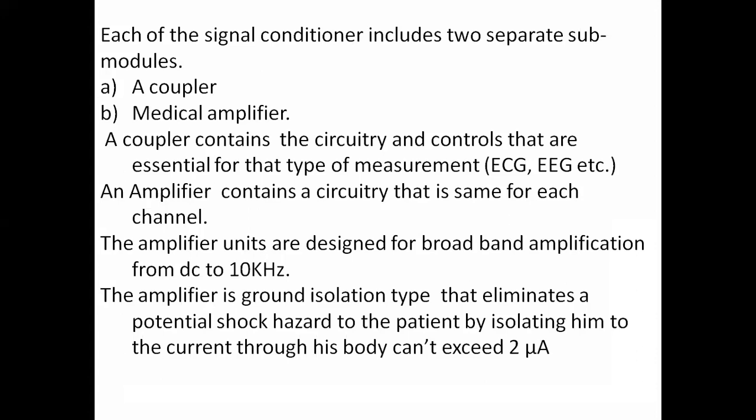Suppose you consider an ECG module. For the ECG module, first of all, we have to couple this module with the actual electrode system. We have a lead electrode system there, so we have to connect this coupler to the lead electrode system, and from that we have to control different parameters. We have to calibrate the system, and after that some amplification will be required.